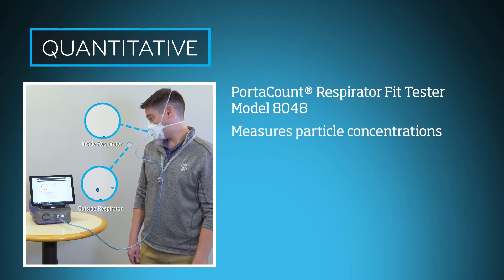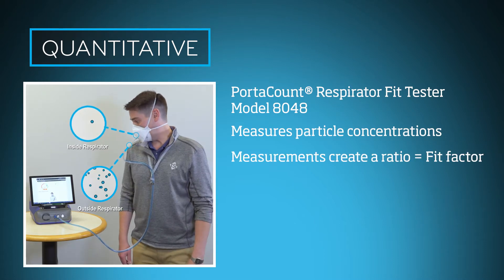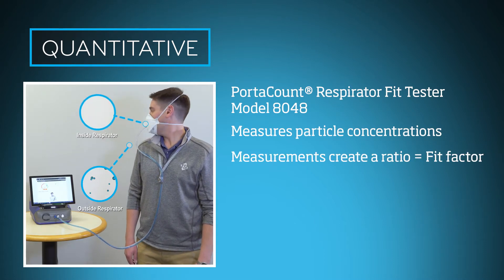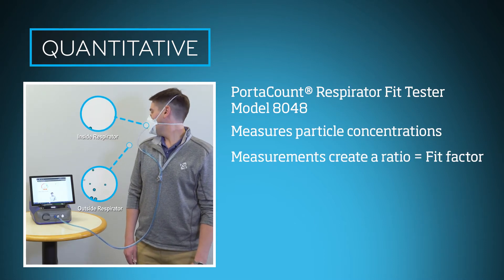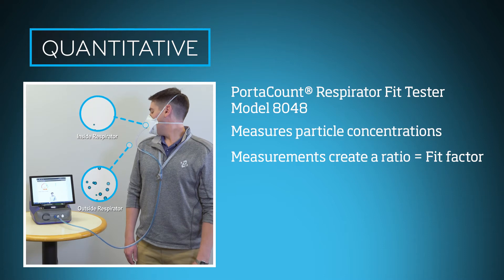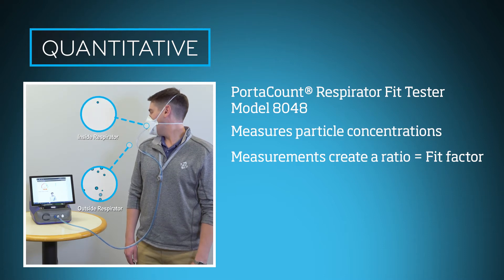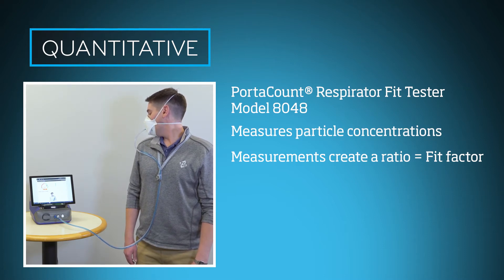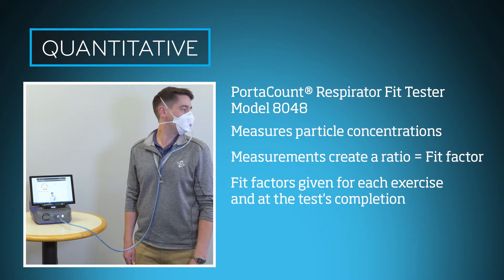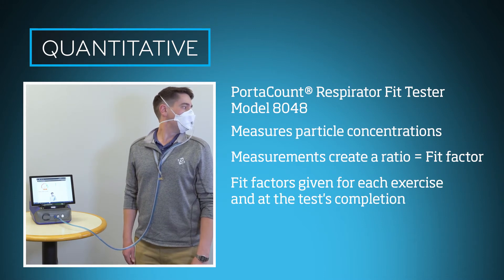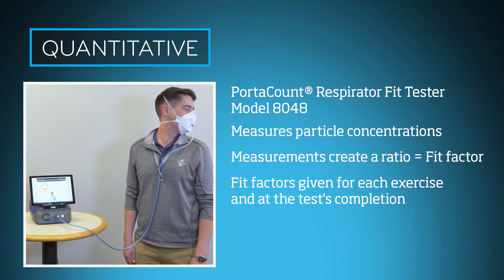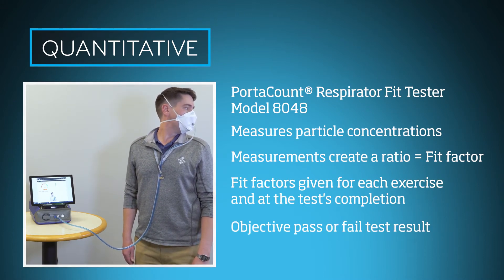Those two measurements create a ratio called a fit factor. Measurements are taken continually throughout the test, and a fit factor is calculated for each exercise and at the completion of the test. This final fit factor is compared to established guidance for respirator types, resulting in a passed or failed fit test.